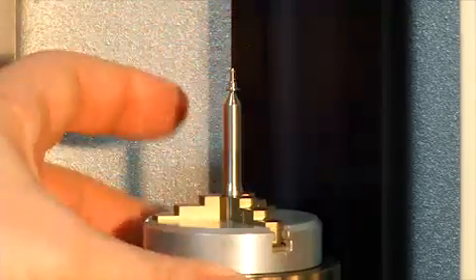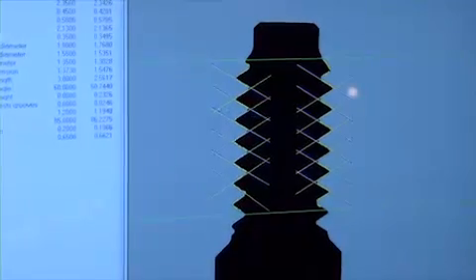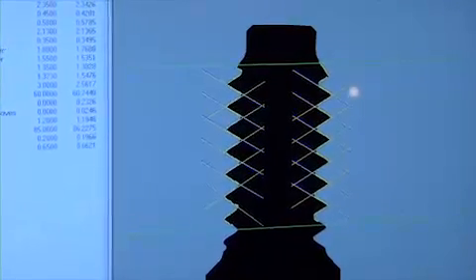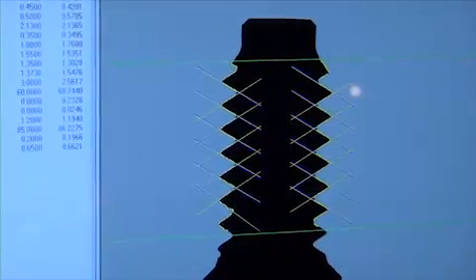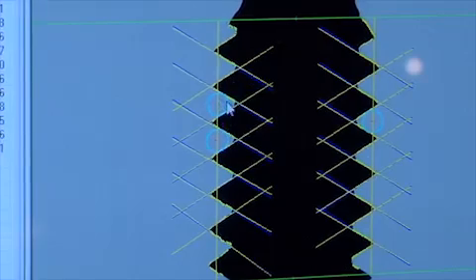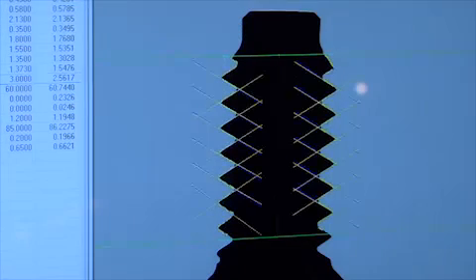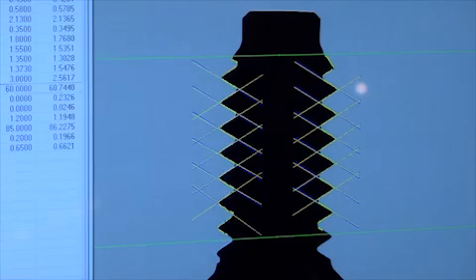A special feature of the Vici is its ability to measure threads. For example, based on a database of threads, it calculates all of the nominals and is able to give you the thread pitch, nominal diameter, medium diameter, the core diameter, roll dimensions based on gauge diameters, useful length, the crest angle, and the crest height.